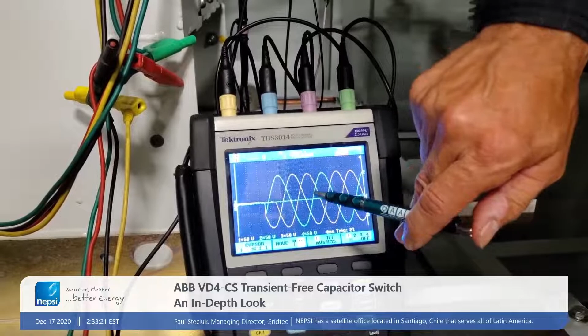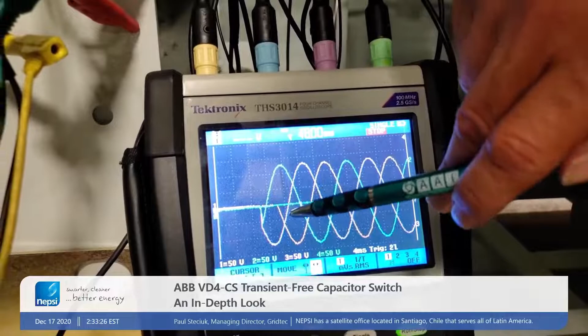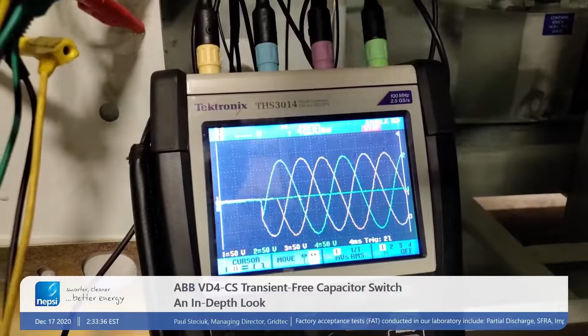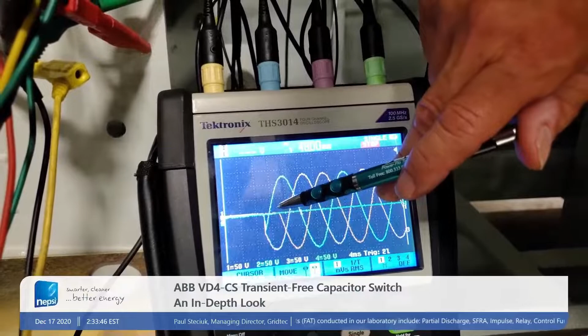Phase A is the orange. It's the yellow. Oh, yellow. Phase A is, okay, is orange from my perspective, yellow. So yellow is closing here. So you can see that operating. The green is the neutral. And you can see that the neutral tracks along 0 because we're monitoring the neutral voltage during the closing operation. So the phase A, when it was switched in, is exactly 0. So the switch is performing correctly.